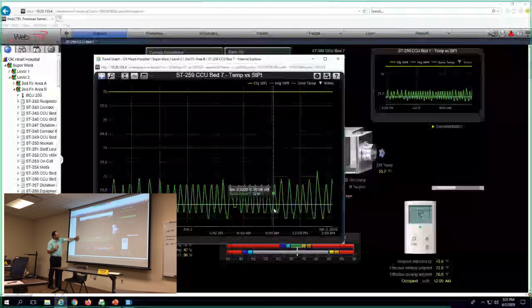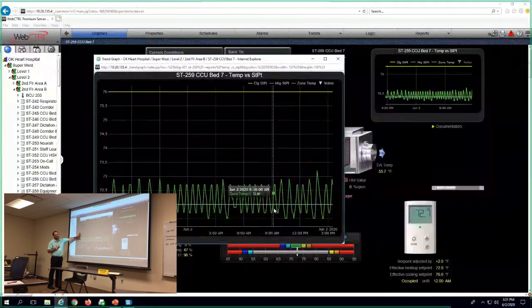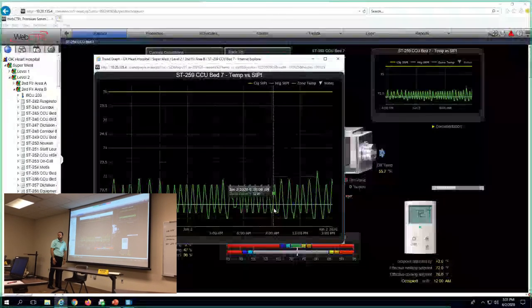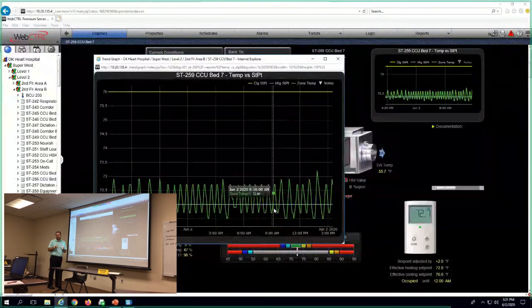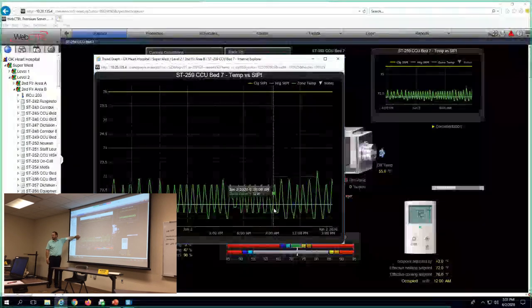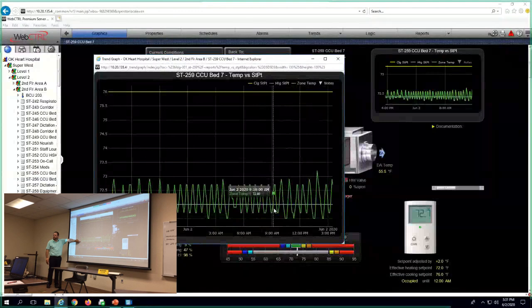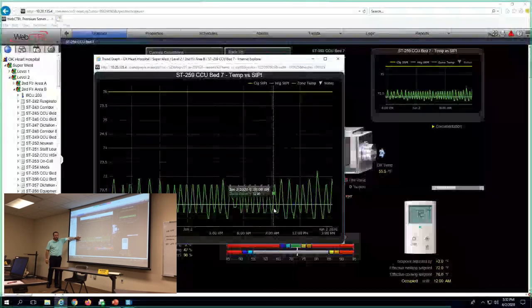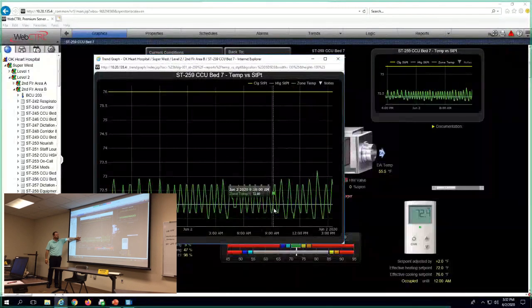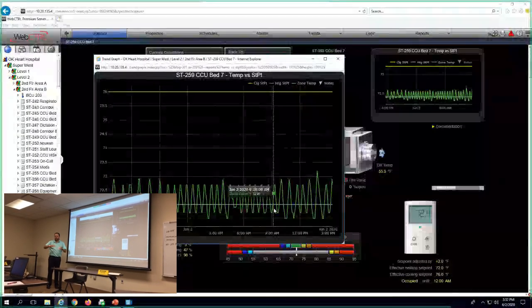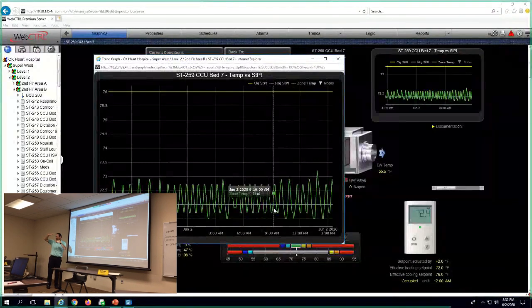In my opinion, this deadband probably needs to be like 74, and then it probably wouldn't look as crazy as it does. But it's actually controlling to the space set point, or heating set point. On your Johnson system, you have a set point. Let's say our set point is 73; would it look the same on Johnson, except you would have one set point? Yeah, you've got one average number that you're riding up and down. That's the difference: we have 2 set points, basically, cooling and heating, because there's the deadband for energy conservation between the cooling and heating set points.